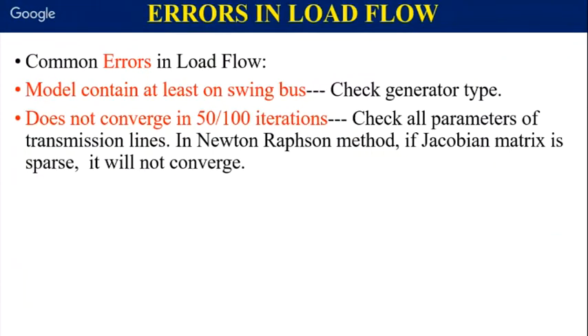Coming back to our presentation, this we have done. Errors that occur in load flow are usually: the model should contain at least one swing bus. That is very general. If there is no swing bus, you will not get load flow. So you should check every generator type. There is a parameter for generator type where we have entered swing bus and PV bus, that you should check. If you correct that, this error will be eliminated.